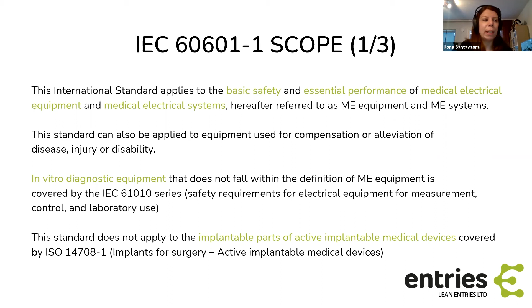But in vitro diagnostic equipment, so if you have laboratory equipment that goes under IVDR and not MDR, those do not fall within the definition here. So there's a different standard series. It's IEC 61010. So the numbers are in a different order, but the difference is substantial. And the standard also doesn't apply to implantable parts of active implantable medical devices. So implantable devices that also have active properties or are using electricity, basically. Those are covered by ISO 14708 because those are very different from other electromedicals.